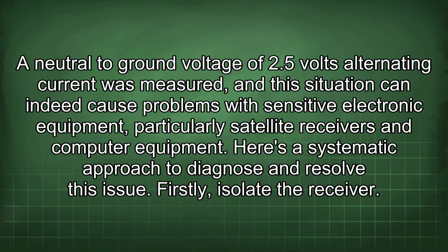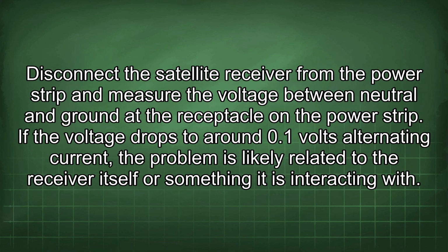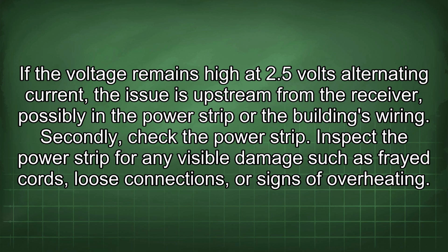Firstly, isolate the receiver. Disconnect the satellite receiver from the power strip and measure the voltage between neutral and ground at the receptacle on the power strip. If the voltage drops to around 0.1 volts alternating current, the problem is likely related to the receiver itself or something it is interacting with. If the voltage remains high at 2.5 volts alternating current, the issue is upstream from the receiver, possibly in the power strip or the building's wiring.